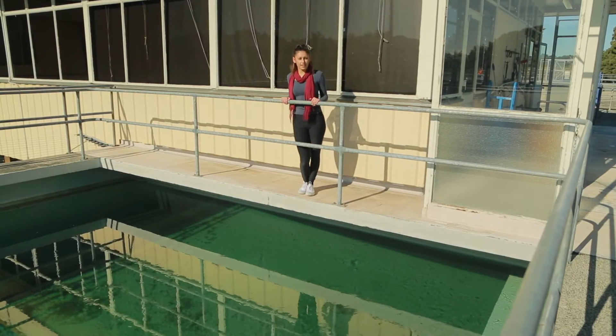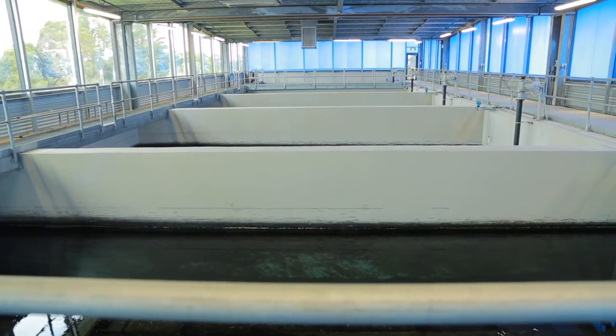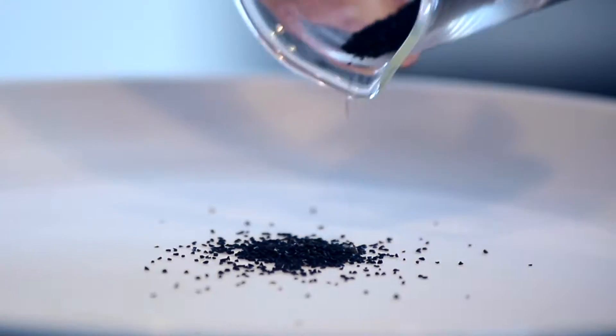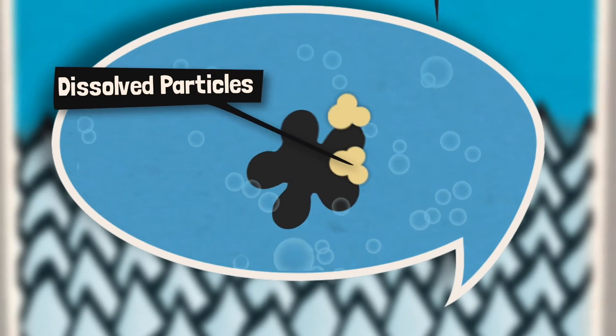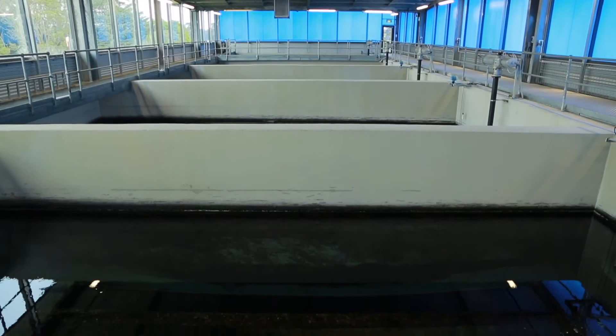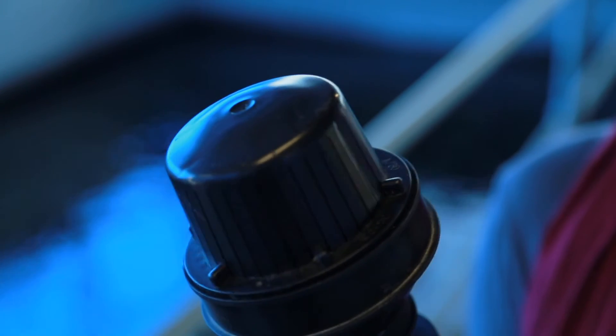This water looks pretty good — we now know it's been screened a couple of times, had chemicals added to remove all the dirt, and been filtered to remove the large microscopic bugs. This is the granular activated carbon room. Granular activated carbon has a huge surface area, with each grain of carbon covered with tiny gaps and holes. This helps the carbon absorb any particles not able to be removed in earlier steps of the treatment process. It also helps if there are taste and smell problems caused by algal blooms in the water source. These tanks have heaps of cone-shaped filters that let the water pass through but trap the tiny carbon particles so they stay in the tank and keep working.